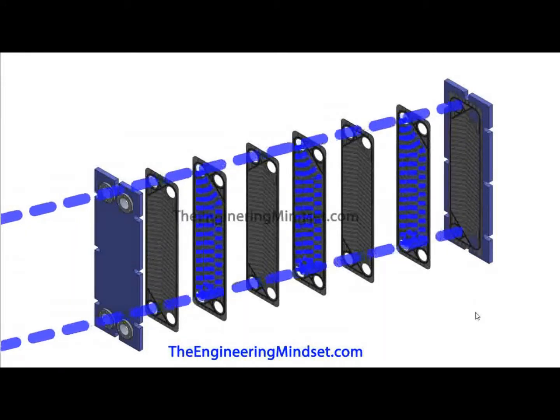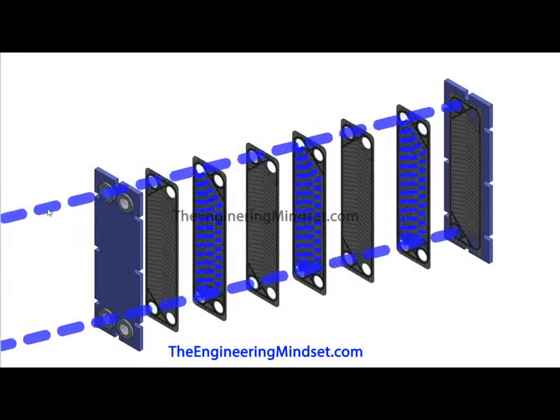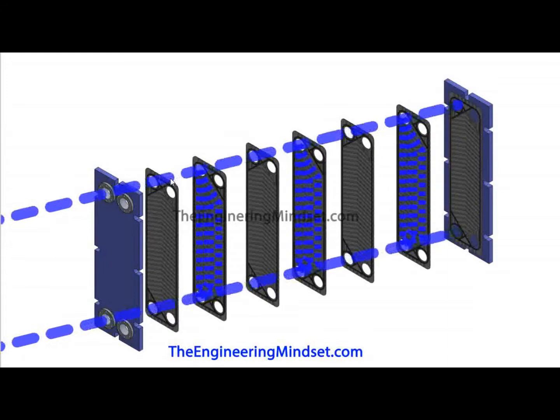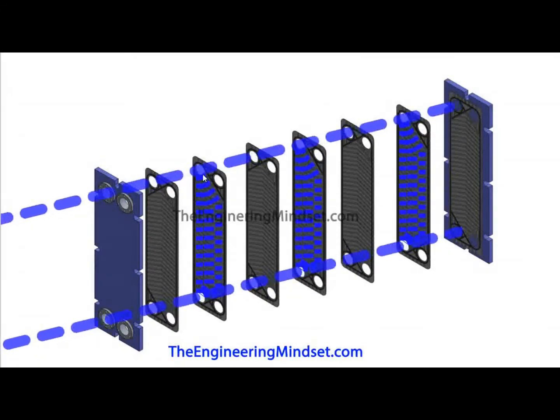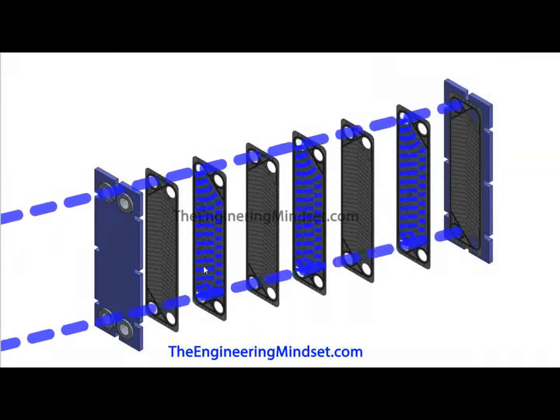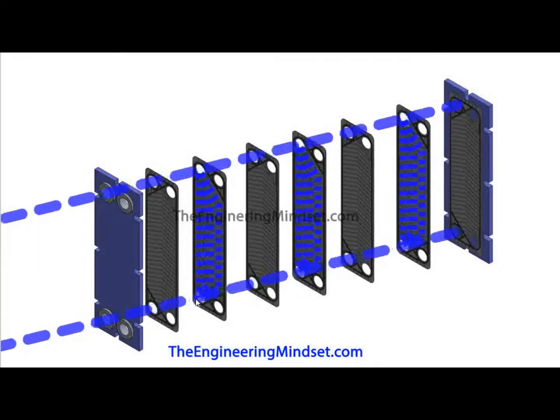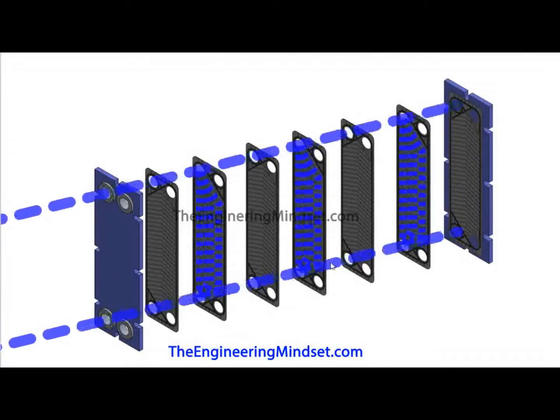If we pass one fluid through, entering through this top port, it passes all the way through - it can't pass through this one because there's a seal there. At the next plate, there's no seal, so it passes through. It can't go into this hole, but it can go into this one because there's no seal. So it all passes through, collects up, and makes its way back out.